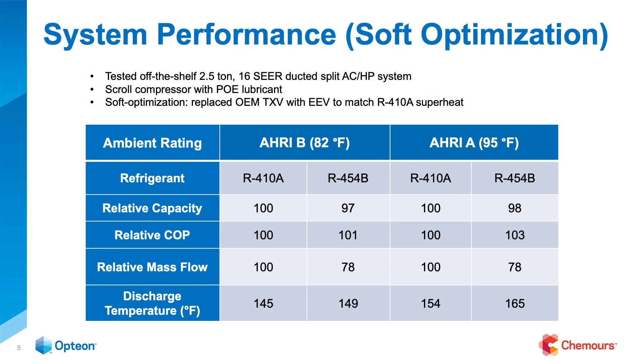The next step we often do is what we call a soft optimization or drop-in test. We take a piece of equipment — this is something you can't do in the field because 454B is going to be for new equipment only — and put it into a laboratory system making as minimal changes as possible. In this case, we changed the thermal expansion valve to an electronic one to match superheat for comparison. You see the performance here: a little bit lower capacity, a little better COP or energy performance, and the operating pressures and temperatures right on the money — very, very close. Nothing too far out of bounds that's going to cause concern or be drastically different when servicing 454B systems compared to 410A.